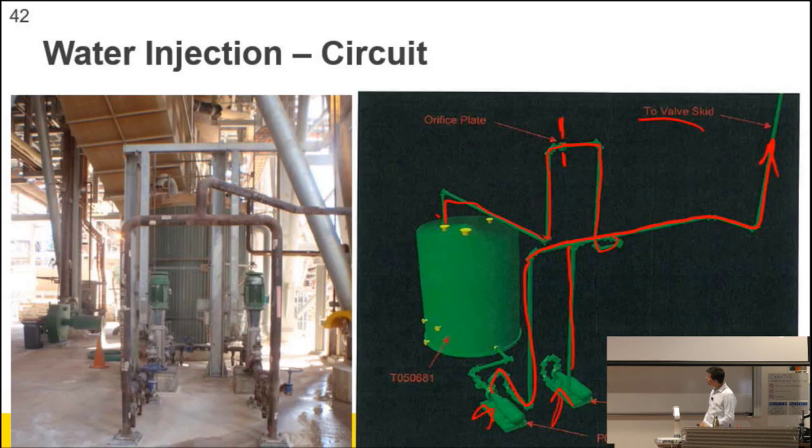So the theory was here that when the valve at the top is closed, right, you'll build up a static head of 1.45 megapascals of pressure in this pipe, and all of that will flow through this little throttle, and we'll look at what the throttle looks like in a moment. The whole product of the pump will go back into the tank.